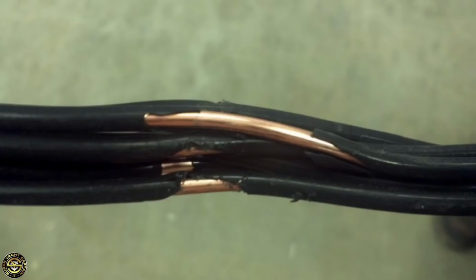So we go back to our cable. The outside, the thing that protects you from the current that's flowing through the copper wire inside, had failed on all three elements. Remember, the earth had that massive resistance, the 105,000 ohms. The earth wasn't functioning. The job of that earth was to take that live current from the metal casing and send it back to the bus bar safely so nobody gets shocked. But the earth had failed, or it was failing. So because the insulation had failed on the elements, the current was transferring into the metal case.